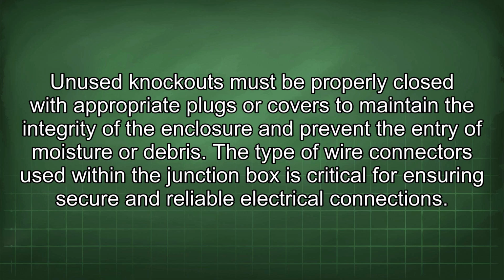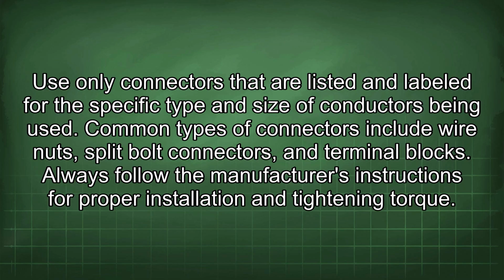The type of wire connectors used within the junction box is critical for ensuring secure and reliable electrical connections. Use only connectors that are listed and labeled for the specific type and size of conductors being used. Common types of connectors include wire nuts, split bolt connectors, and terminal blocks. Always follow the manufacturer's instructions for proper installation and tightening torque.